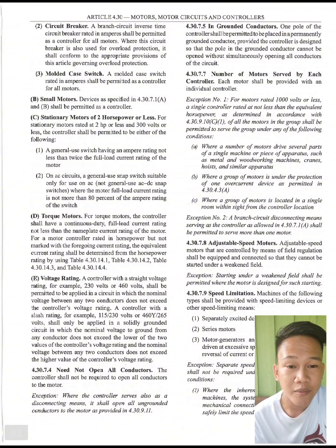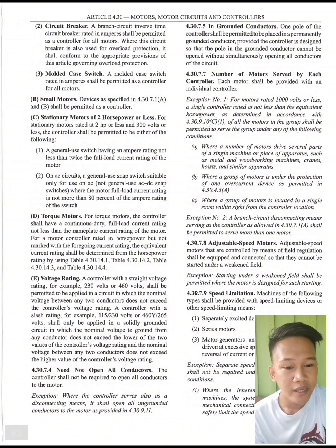4.30.7.9 Speed limitation. Machines of the following type shall be provided with speed limiting devices or other speed limiting means. First, separately excited dc motors. Second, series motors. Third, motor generators and converters that can be driven at excessive speed from the DC end, as by a reversal of current or decrease in load.